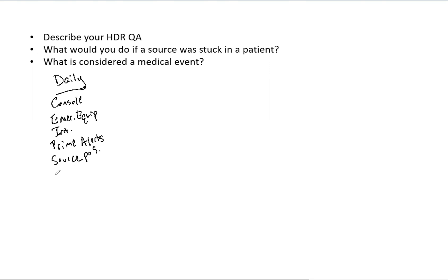You want to verify your activity of your source, that your source retracts when you do a lot of the emergency procedures, open the door, things of that nature. And then any other procedures you do for your daily QA.